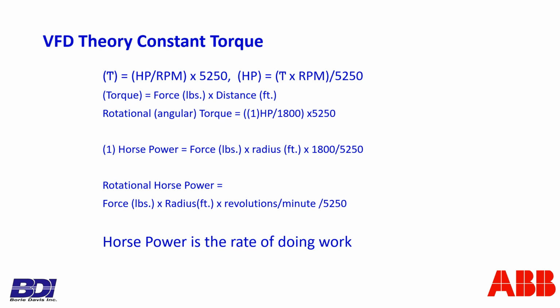Solving for torque in the first equation here, torque equals horsepower divided by RPM times 5250. Or we could solve for horsepower, which is equal to torque times RPM divided by 5250. And let's just assume we're a 1 horsepower motor. Well, the rotational torque would be equal to the horsepower, 1 horsepower, divided by, if we're using a base speed 1800 RPM motor, times 5250. If you do that math out, you'll see that we wind up with 5250 divided by 1800. That's about that 3 foot-pounds per horsepower.